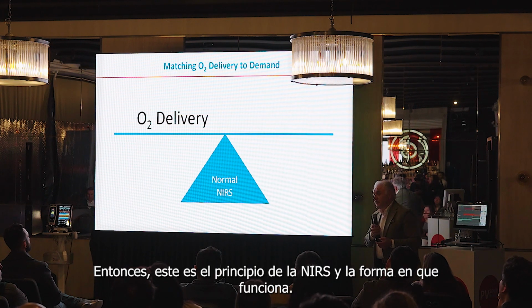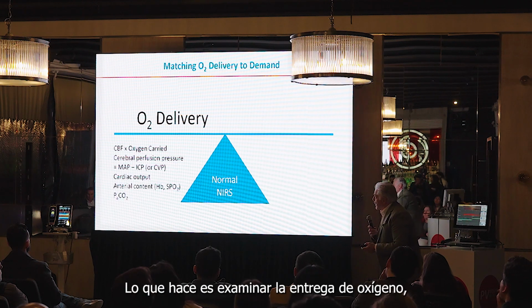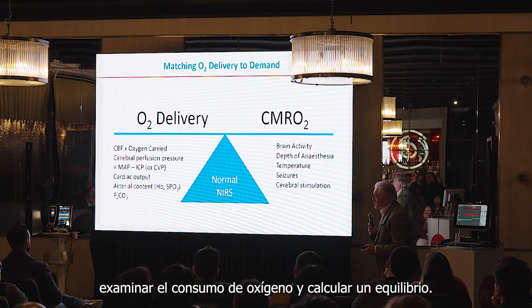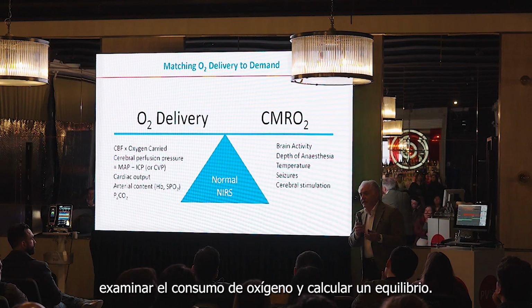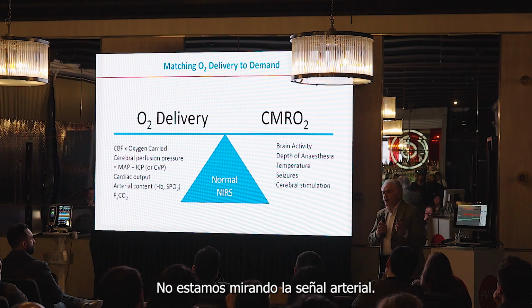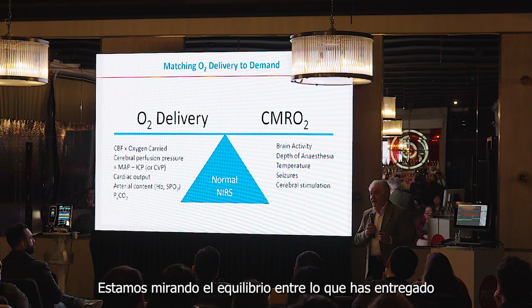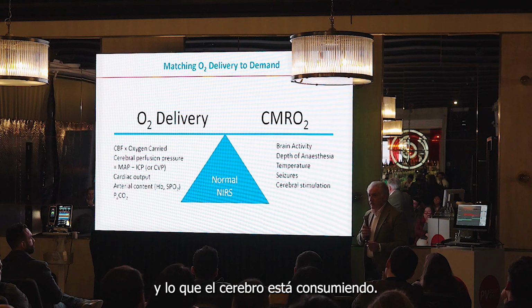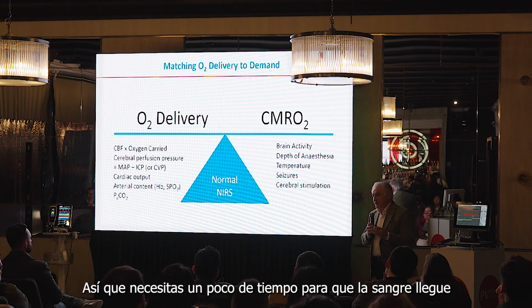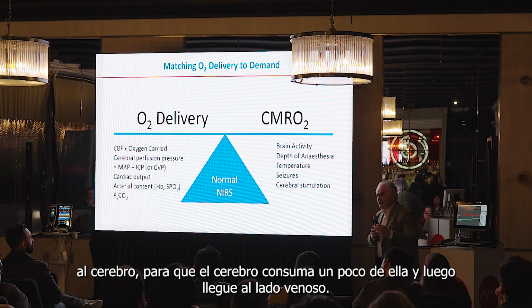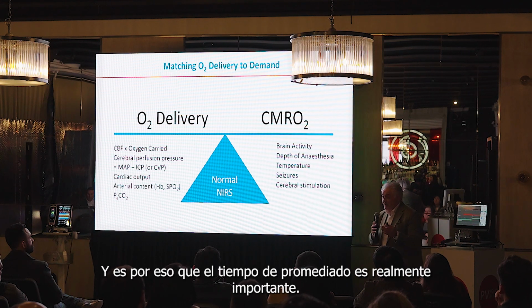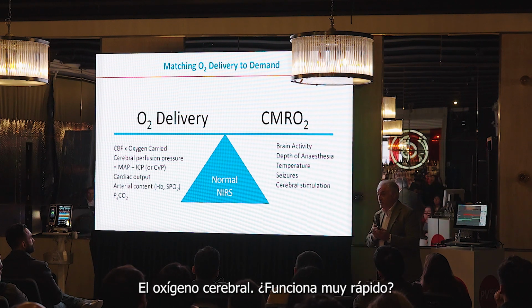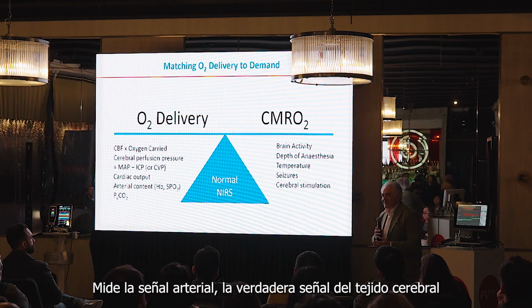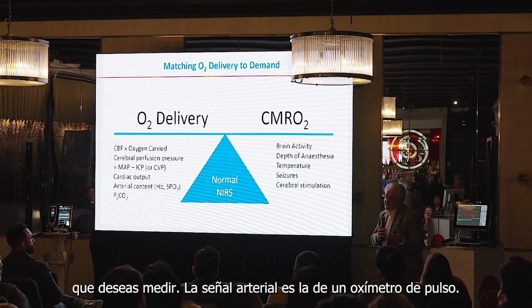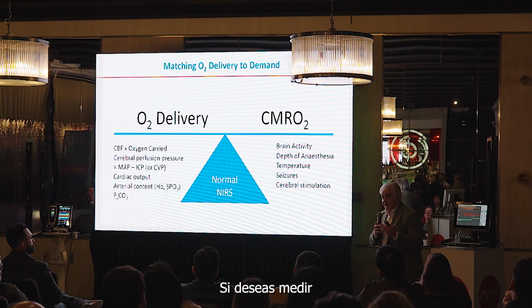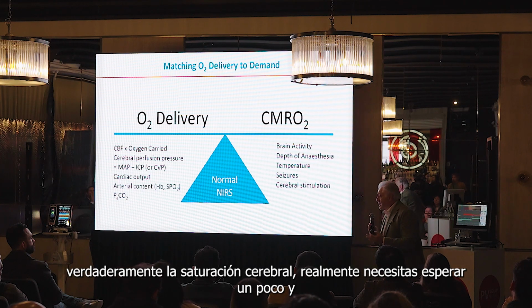So this is the principle of NIRS and the way it works. It looks at oxygen delivery, looks at oxygen consumption, and works out a balance. So NIRS is not like pulse oximetry. We're not looking at the arterial signal. We're looking at the balance between what you've delivered and what the brain has consumed. So you need a little bit of time for the blood to go in, the brain to consume a bit of it, and then get it into the venous side. And that's why the averaging time is really important. Cerebral oximeters that work too fast measure the arterial signal rather than the true tissue brain signal. If you want to measure the arterial signal, use a pulse oximeter. But if you want to truly measure the brain saturation, you really need to wait a little bit.